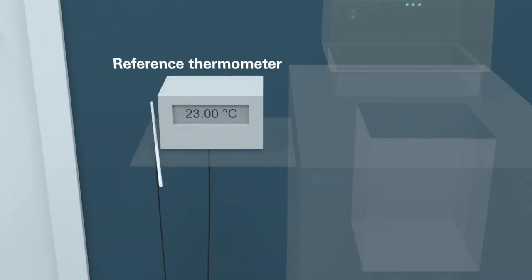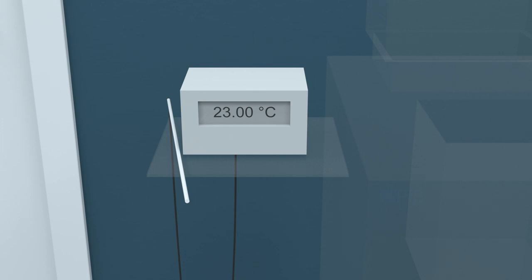You will also need a calibrated reference thermometer to determine the temperature of the water bath. The reference thermometer needs to provide a measurement uncertainty of no more than 0.03 degrees Celsius for a coverage factor of 2. It must be traceable to national standards.